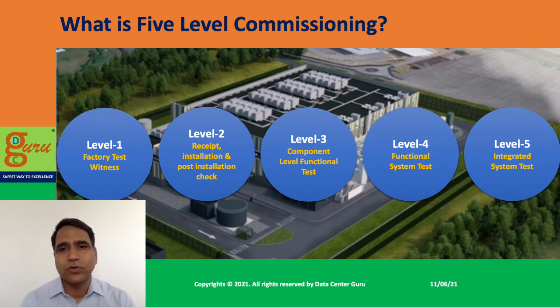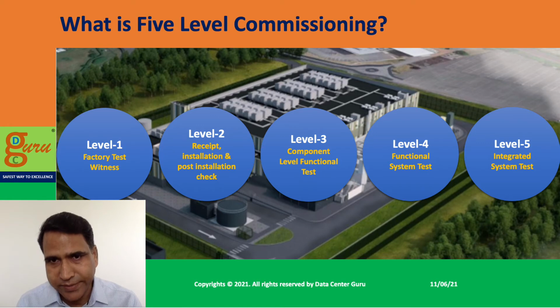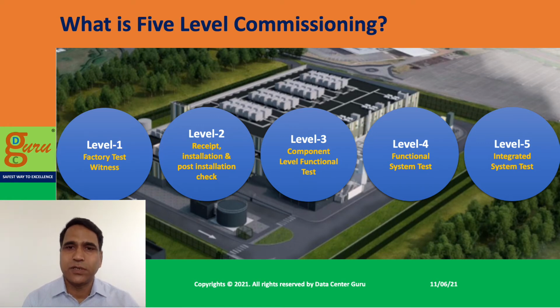Level 4 talks about system functional tests - like UPS in redundant mode, cooling in redundant mode with chillers, PAHUs, and so on. Individual systems have to be tested to see that they are able to perform at the level required, and also deliver the level of redundancy or reliability specified in the beginning. These individual system tests are covered under level 4, which we call individual functional system tests.